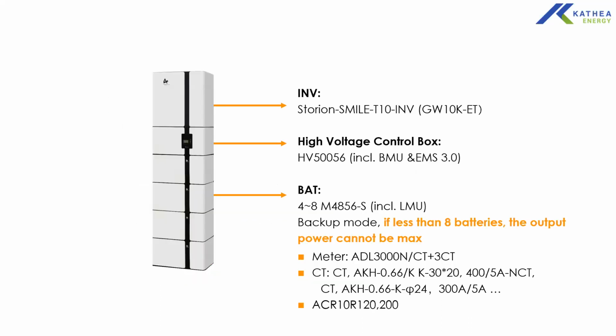So the top part is an inverter, the 10 kilowatt inverter. Please take note that a 10 kilowatt inverter is split between 3 phases. So it's basically a 3.3 kilowatt inverter on each phase. So when you're doing load specking for a 3-phase system, please take note of that. Make sure your peak power on each phase does not exceed 3.3, because on a 3-phase inverter, if one of the phases fails, the whole system shuts down. So please take note of that.